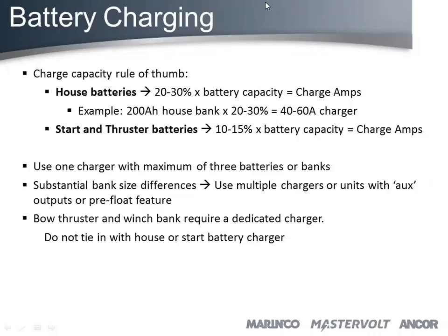For thrusters and starting batteries, we don't need to go that high. 10 to 15% on average is fine. There's no load connected to it. You typically are plugged in or run the generator, the batteries are full, and it will recover that way. Another thing is I still see a lot of boats, Mike can probably confirm that, coming in from Asia, where we have one charger charging 5 different battery banks. It's not going to work. That battery charger, even though it's distributed on demand, can only focus on the most demanding battery with the lowest internal resistance. If you run all these batteries from one single charger, that's asking for trouble. So only max that out at 3 outputs, 3 different banks, and that's it.